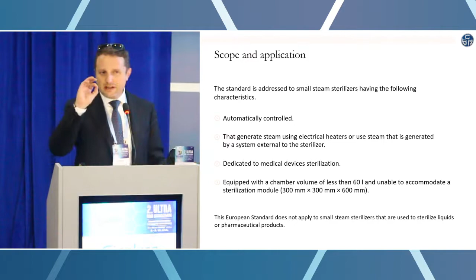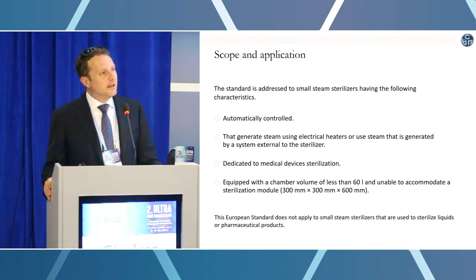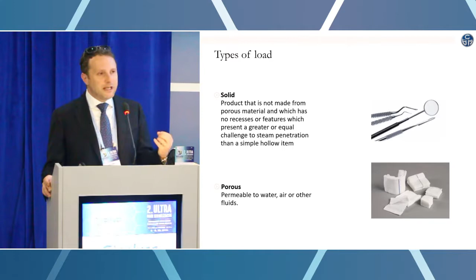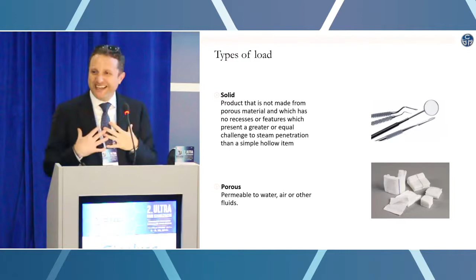And again, speaking about dental handpieces, unfortunately, outside of the hospitals, dental handpieces are not treated so well during sterilization, because often doctors have a couple of turbines or contra-angles, and they do not want to sterilize them between each patient, even if it is, let's say, more or less mandatory. Even because you have to think that when you go to your dentist, I don't want to scare you as much as I'm scared of the dentist, but you have to know that when the turbine that you have in your mouth stops, at the tip of the turbine, a vacuum is created.